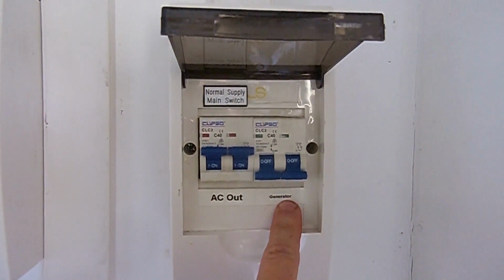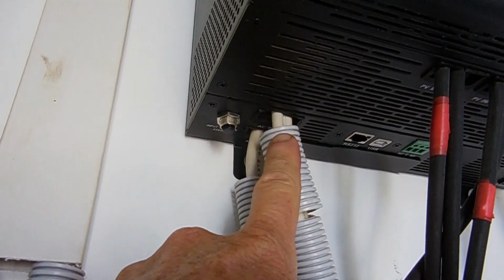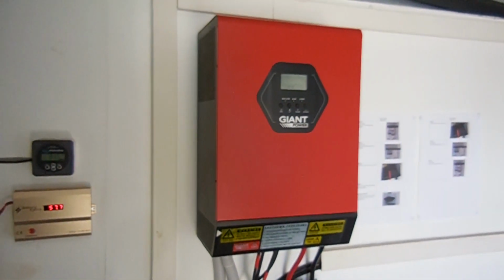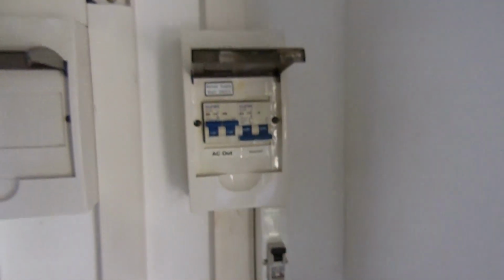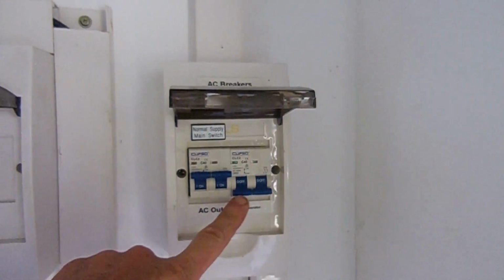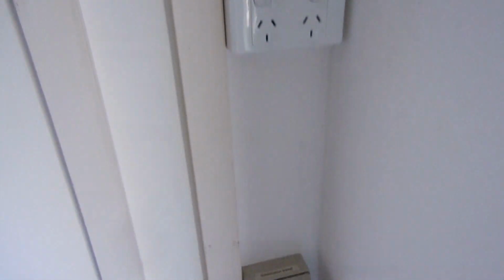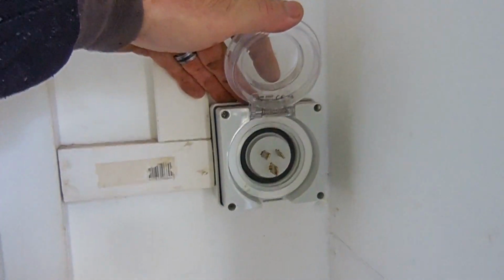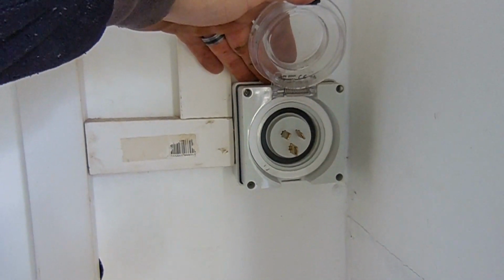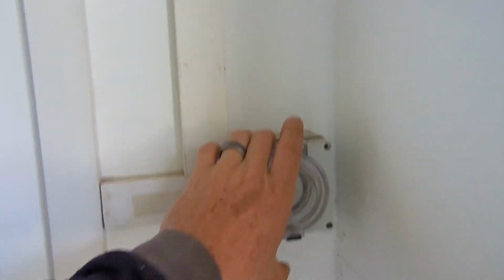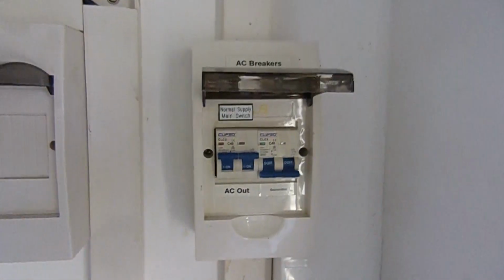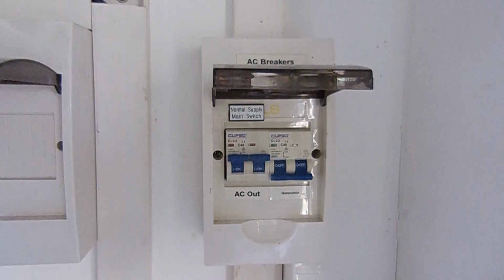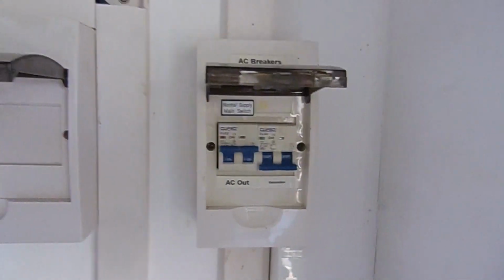We also have a generator input. So we go back to the inverter. This power here, that's the generator input. So if our batteries are low in cloudy weather, or a few days of cloudy weather, something like that, we have our DC breaker for the generator, which is turned off at the moment. We have a power point down here. We can just plug a generator into here. We have a 2 kilowatt inverter generator which we can plug into there and just start that up. Switch this breaker on, and then the house will run off the generator and charge the batteries at the same time through the inverter.